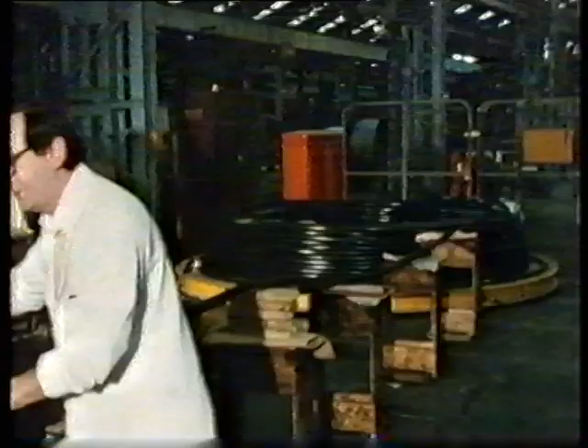Now comes one of the most skilled operations of the whole process, the jointing together of the cable sections into one continuous length of 16.5 kilometers. First of all, the cable ends are stripped back to the copper conductors, which are then brazed together. Next, the black carbon papers are reinstated, ensuring continuity across the jointed section.